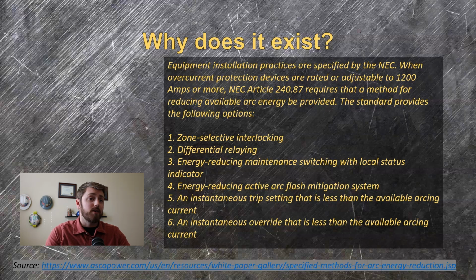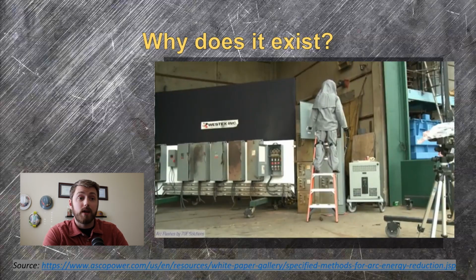Secondly, nearly all breaker trip settings, long time, instantaneous, short time, ground fault, under voltage, whatever, are designed and coordinated to protect the expensive power equipment or keep the cabling in the walls from overheating and catching fire. Coordination study engineers need to allow for extremely high currents to flow for short periods of time for things like motor inrush, so that the system works and doesn't trip every time a large load is energized. That wouldn't work. This leads to huge potential current and extremely dangerous levels of energy that can be released in the event of an arc flash.